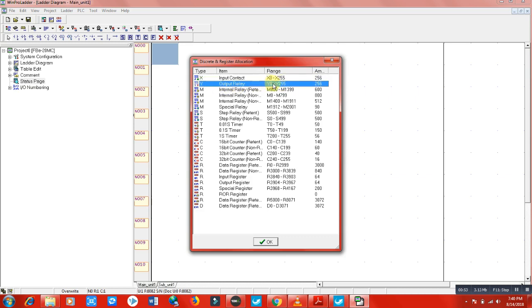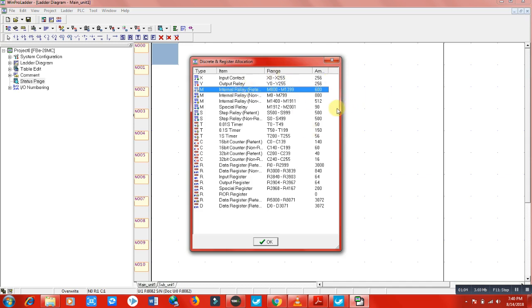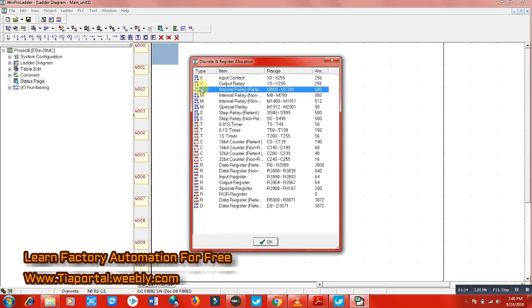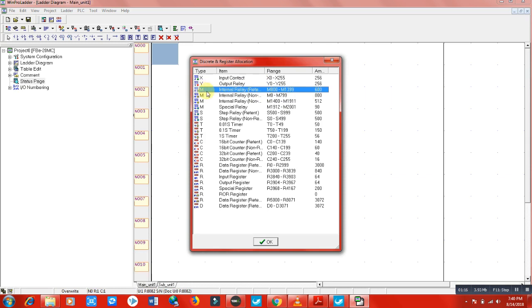We also have outputs from Y0 to Y255. We have internal memories — these are internal relays. Just as we use physical external relays in electrical circuits, here we use internal relays represented by the symbol M, which stands for memory. Some of these memories are retentive and some are non-retentive.